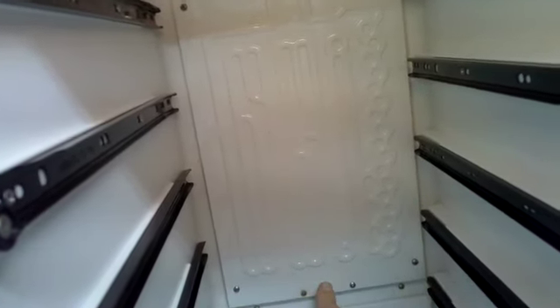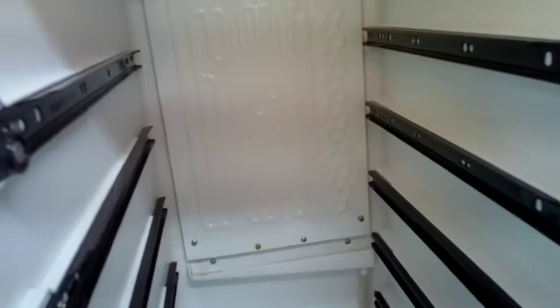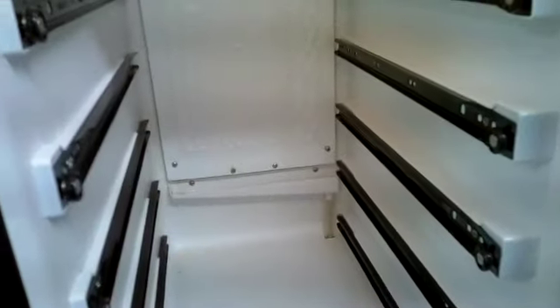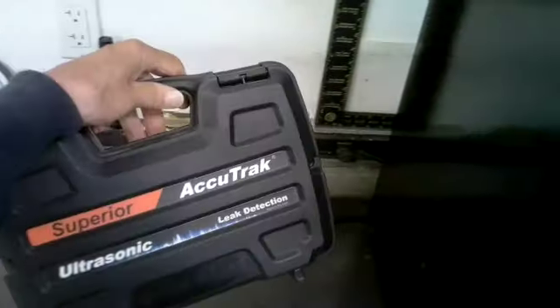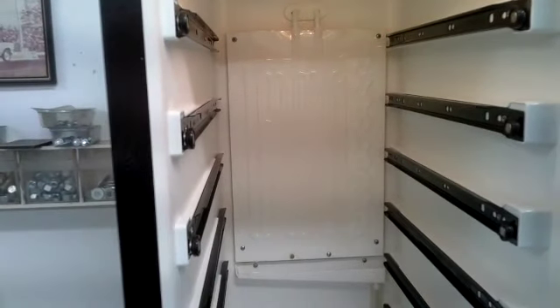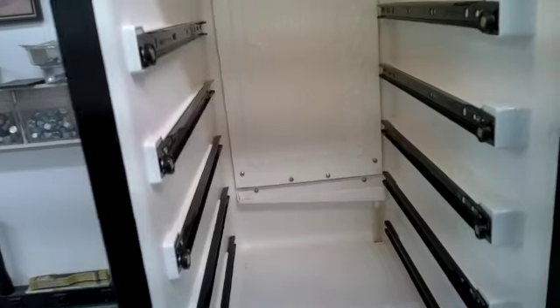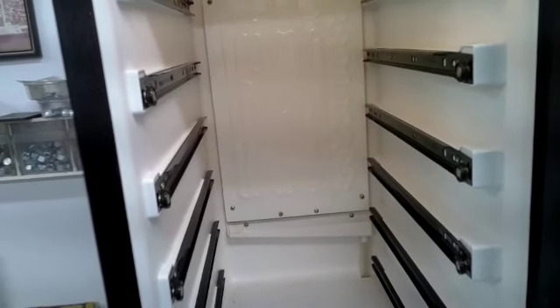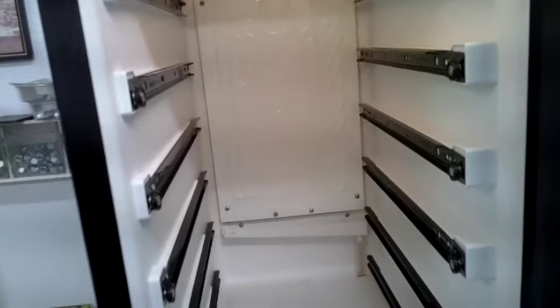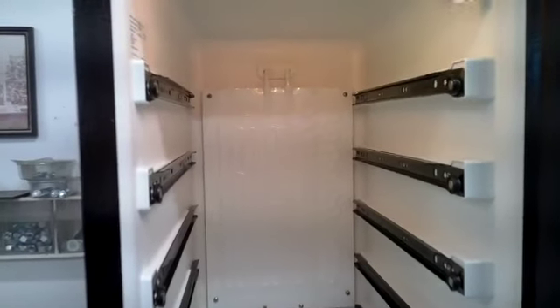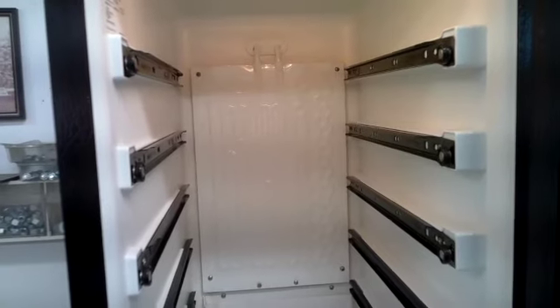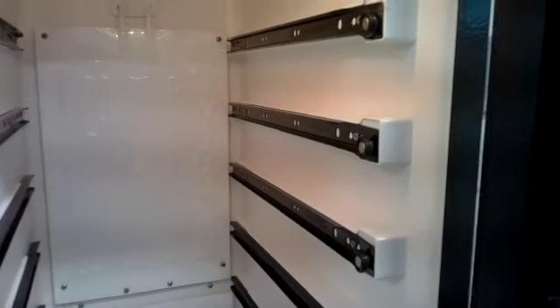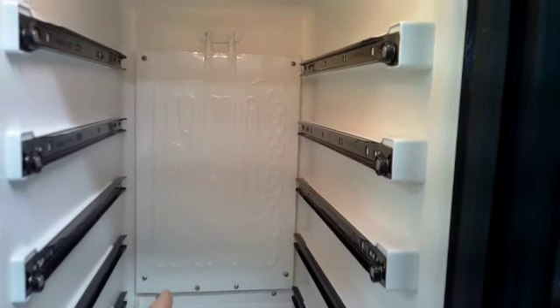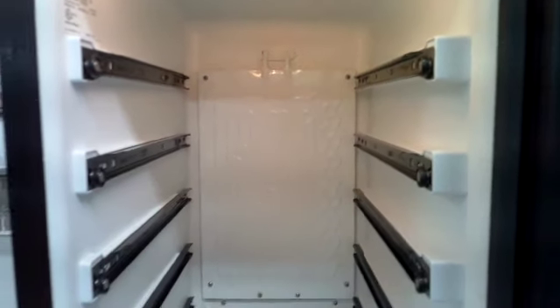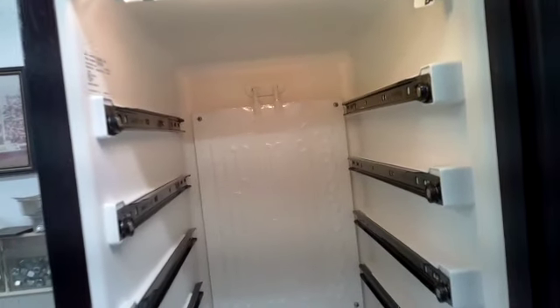So we definitely feel there is a Freon leak in here, and we're going to see if we can find it. And we got our little trusty ultrasonic leak detector here. We're going to see if we can find the leak in this evaporator. In worst case scenario, since Sub-Zero does not make this machine anymore, it's discontinued, and so are the parts. You can't get that evaporator plate anymore. However, there are some other options here. Now, Scotsman makes a machine similar to this and uses that same evaporator plate, so you can get that evaporator from Scotsman. It's very, very expensive.